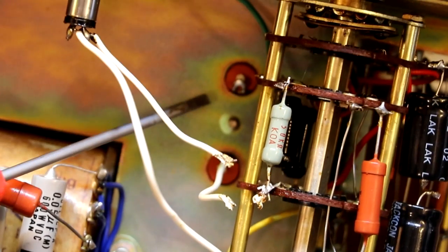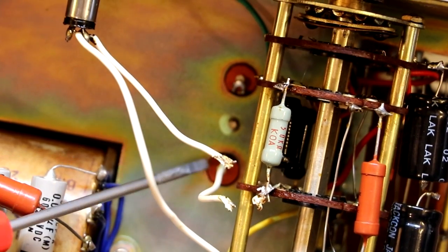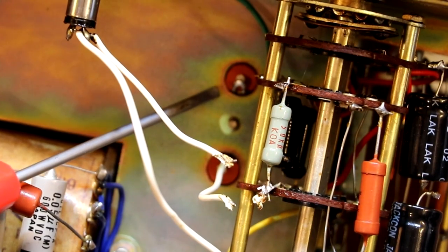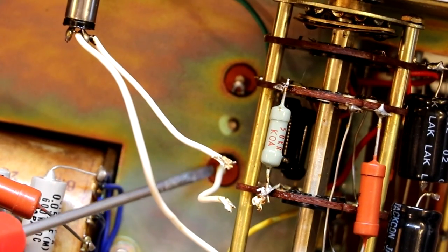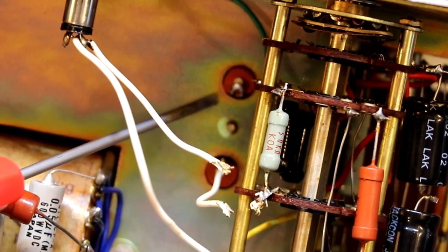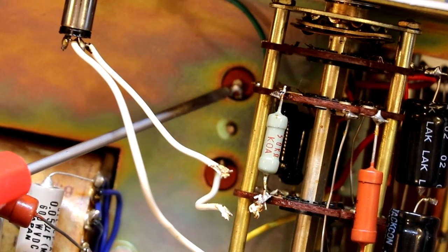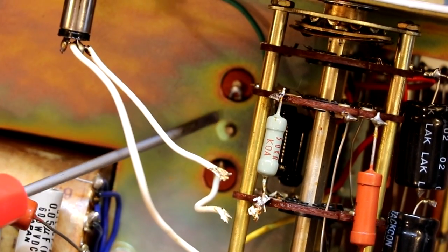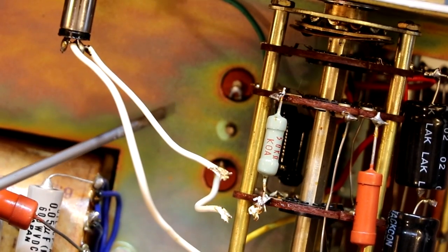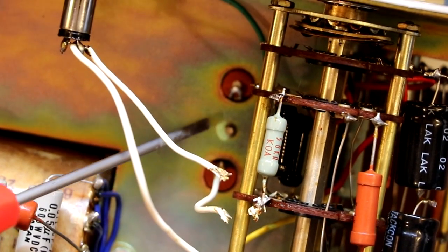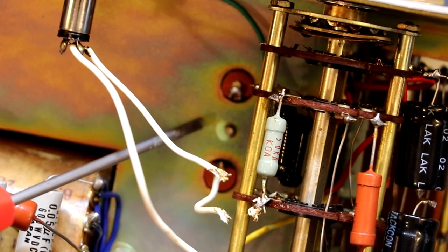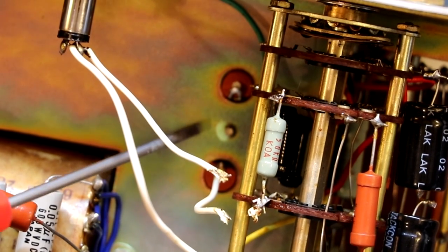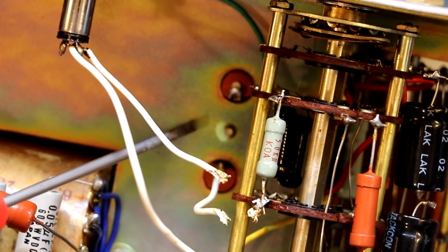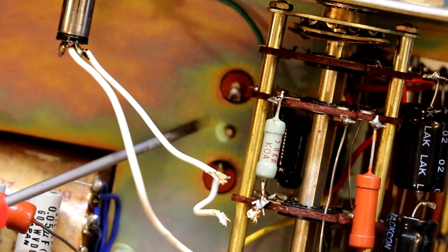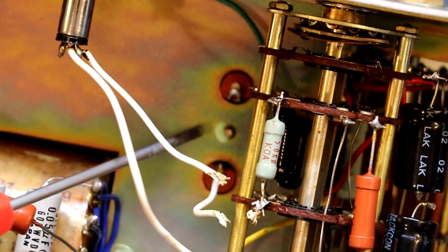I'm not sure if you'll be able to see it on camera, but the actual tag strip for the fuse, where it comes through the metal enclosure, is pretty much touching the metal of the enclosure. There's less than a millimetre gap between the live terminals and the chassis here, so that's certainly no good. So I think at some point we need to change this fuse holder out quite urgently, but I'm going to see if we can just get away with leaving it for now. And I'll come back and change that out separately.